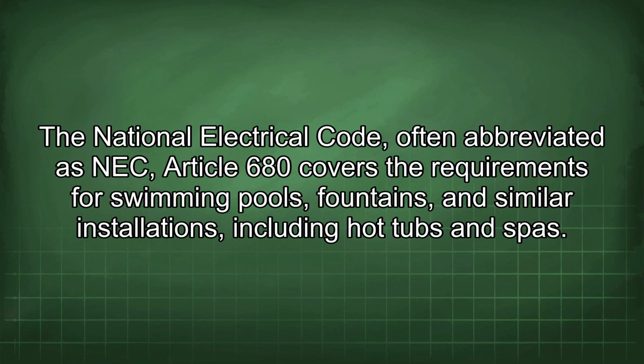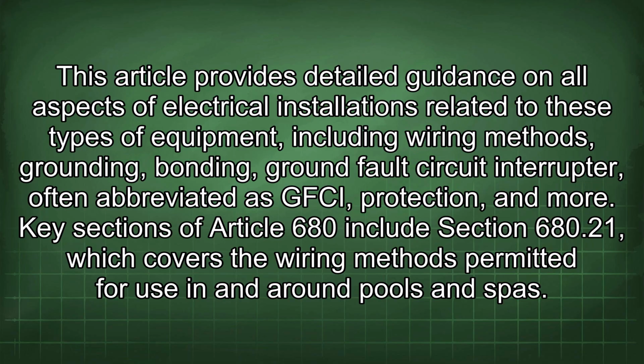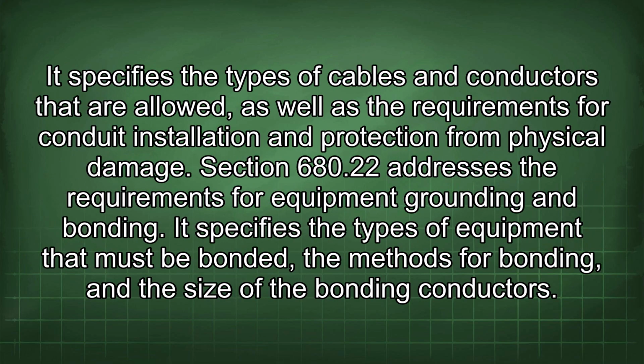NEC Article 680 covers the requirements for swimming pools, fountains, and similar installations, including hot tubs and spas. This article provides detailed guidance on all aspects of electrical installations related to these types of equipment, including wiring methods, grounding, bonding, ground fault circuit interrupter (GFCI) protection, and more. Key sections of Article 680 include Section 680.21, which covers the wiring methods permitted for use in and around pools and spas. It specifies the types of cables and conductors that are allowed, as well as the requirements for conduit installation and protection from physical damage.